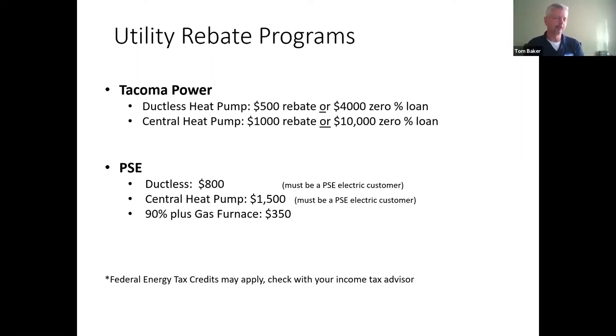I really should have addressed that when I went through that, because that would leave a question just as you've asked. So there is a point at which the heat pump is no longer efficient. There's a temperature at which it can't really do the job of keeping your house warm. We call that the set point, and it can be anywhere depending on your system from 30 degrees to 18 degrees or maybe even lower. So it's important to have a backup heat source, even though we only get a few days a year or maybe even every couple years where we might drop below the worst case scenario, you need to be able to keep your house warm.